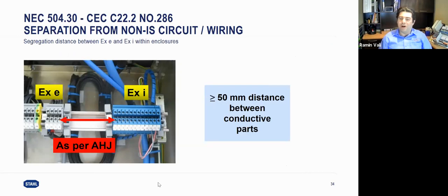The other consideration we always have is about the separation from non-IS signal, because we have to make sure that no fault will be connected to the IS. Especially if we have an IS wiring and we connect it to the high voltage or high current, basically we are eliminating that entity parameter calculation. We increase the voltage above the safety level.